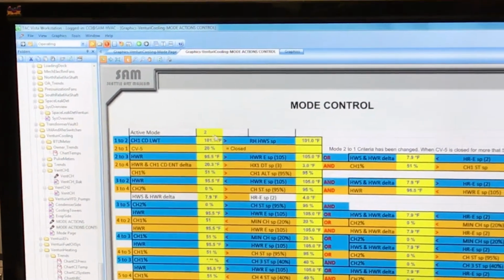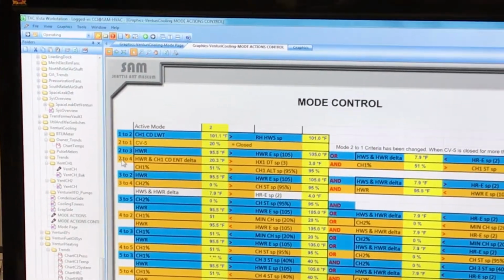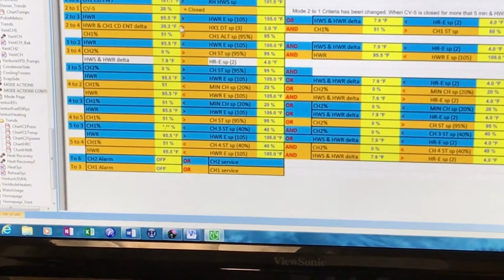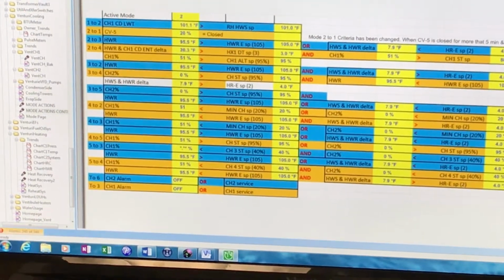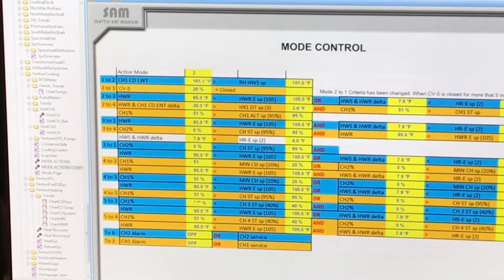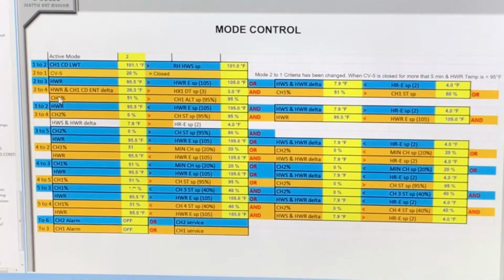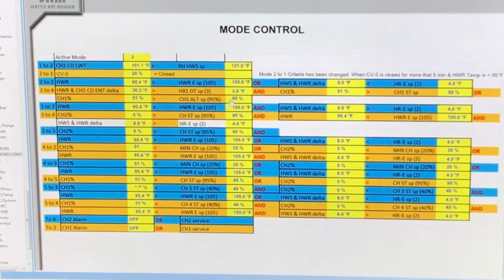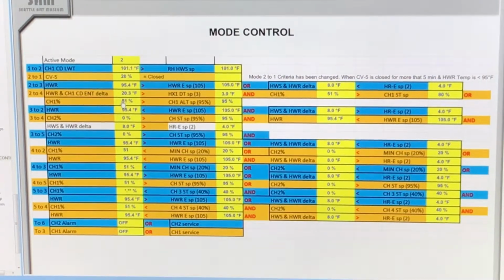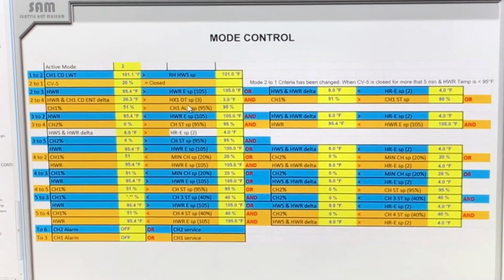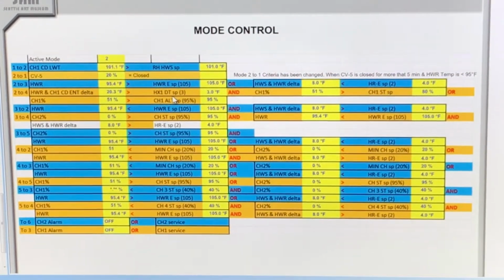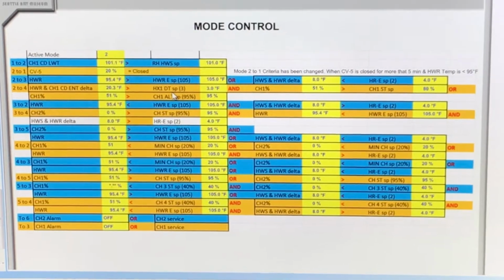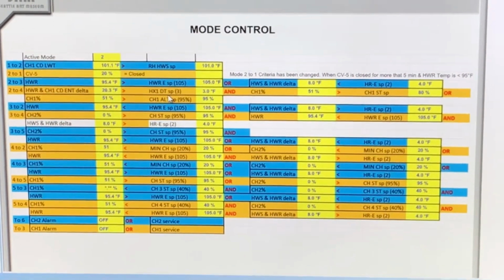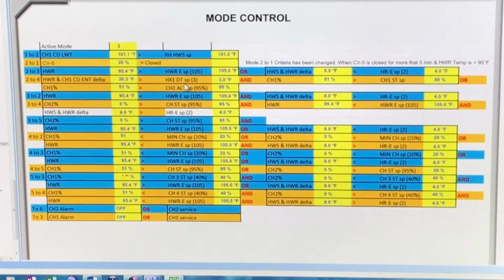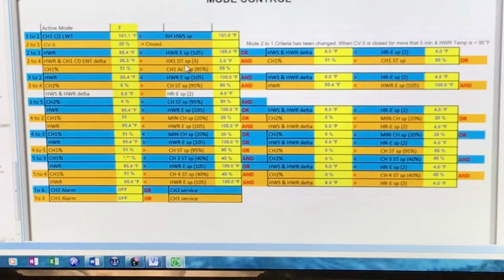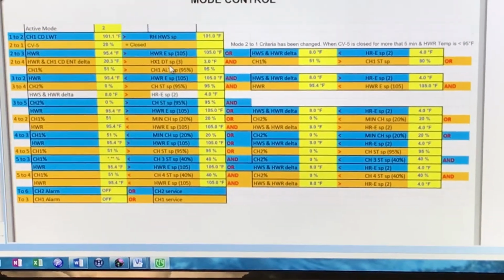Right now you're in 2, and we're only working with the 2s. This 2 to 4 has a statement that says this and this have to be true before it moves to mode 4. Or if chiller 1 percent is greater than 95, this could happen all on its own, with this still being false, and it would still move to mode 4. Say we have a record-breaking summer temperature of 108 degrees outside, very unlikely to ever happen, and then chiller 1 is at 95% of its capacity. At 95% of its capacity, with the delta being higher, it will change to mode 4. Got it. Make sense?